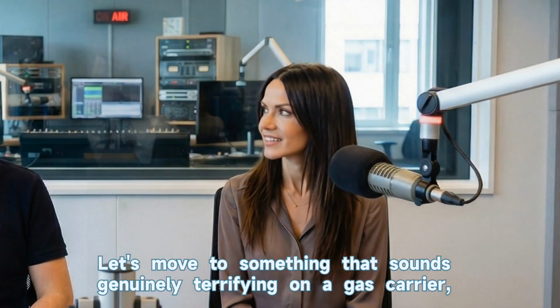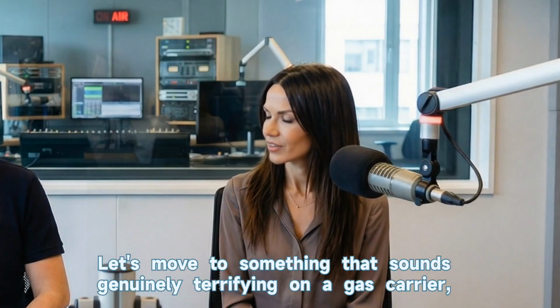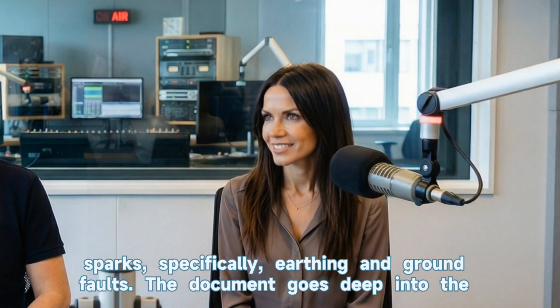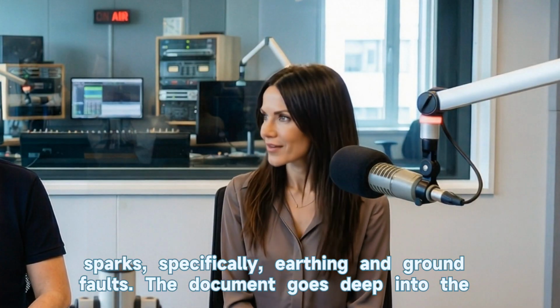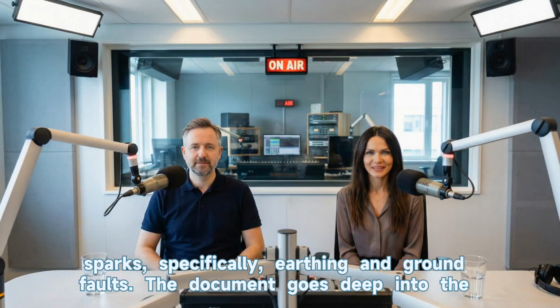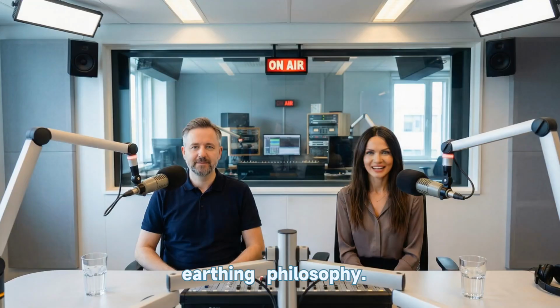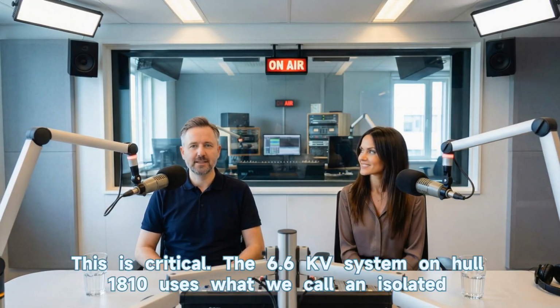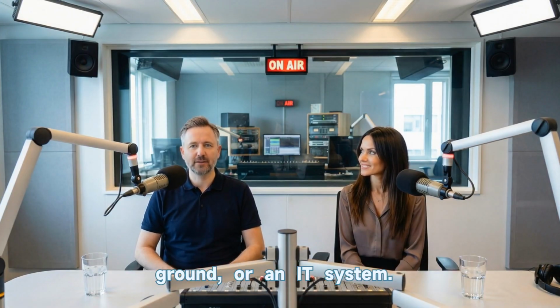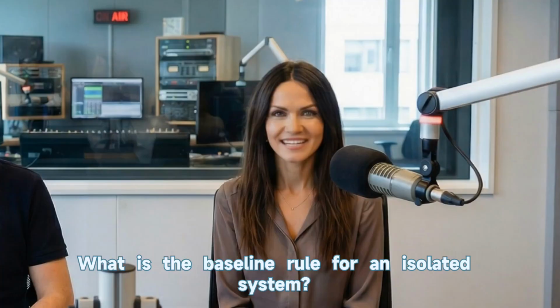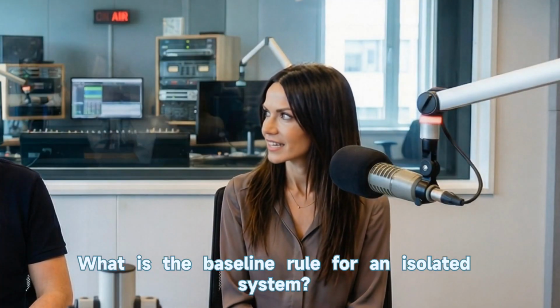Let's move to something that sounds genuinely terrifying on a gas carrier. Sparks. Specifically, earthing and ground faults. The document goes deep into the earthing philosophy. This is critical. The 6.6 kV system on hull 1810 uses what we call an isolated ground, or an IT system. What is the baseline rule for an isolated system?